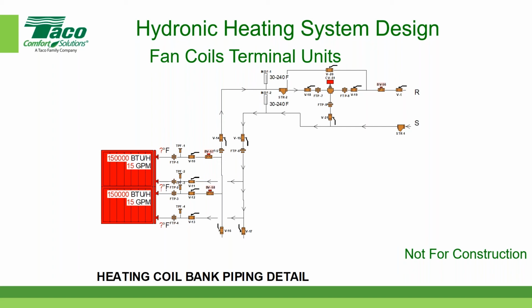Sometimes we will recommend that you put a minimum number of three-way valves on your terminal devices to ensure minimum flow, either required by the boiler if it's a primary variable flow system, or the pump if it's a primary secondary loop. So in this case, it would be a secondary loop. The secondary loop would have a minimum flow required by the pump, and we would select the number of three-way valves to equal the minimum flow required by the pump.